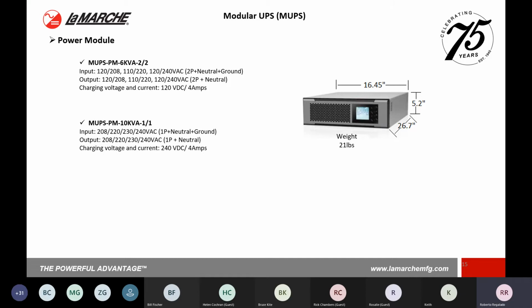It is a smaller current, but again, these are built to be used for smaller backup times, not necessarily more than a 1 or 2 hour type backup. Now, sticking with the same voltage rating, with the same style single to single phase, we're going to go with the 10 kVA module, which is a single to single, two-way 220, 230 or 240 can be set up. It's one line, neutral and ground, and it can follow the same output voltages using a charging voltage and current of 240 volts DC with the 4 amps charging current.